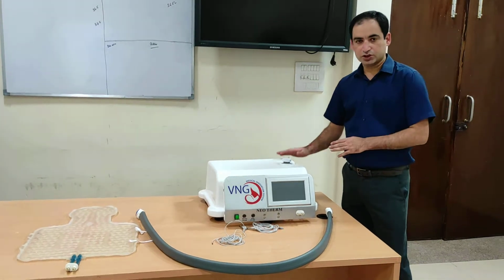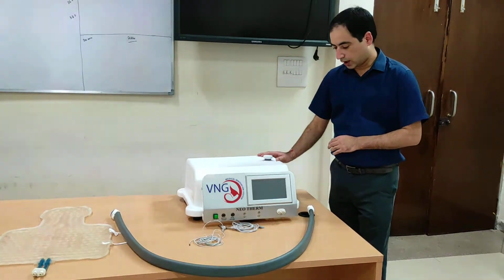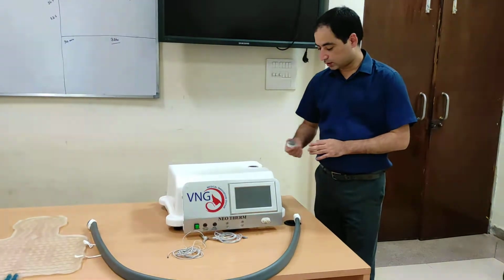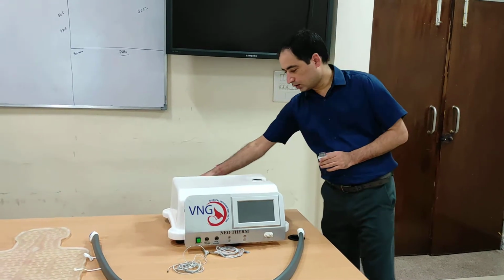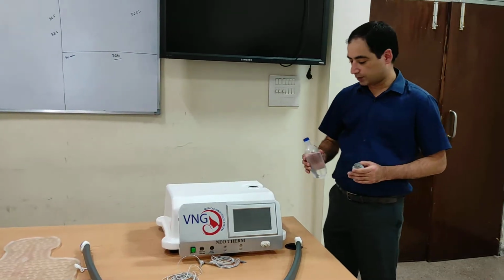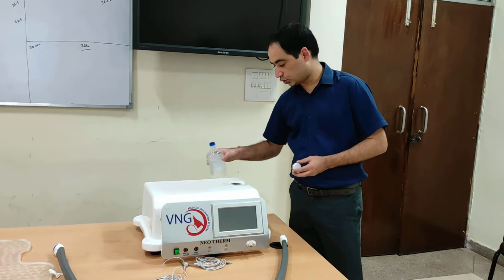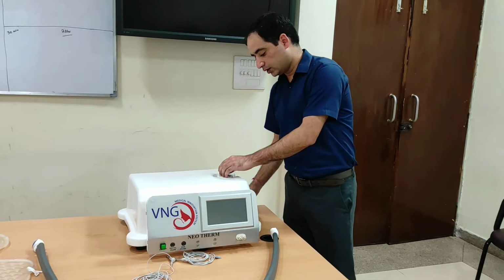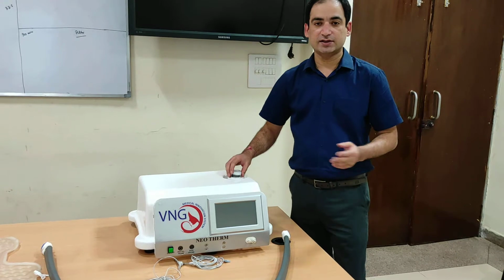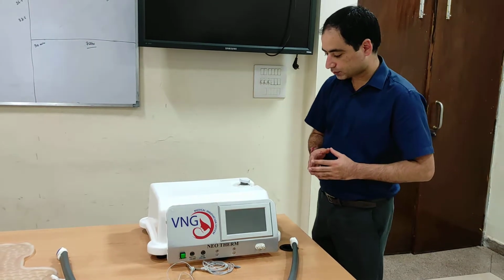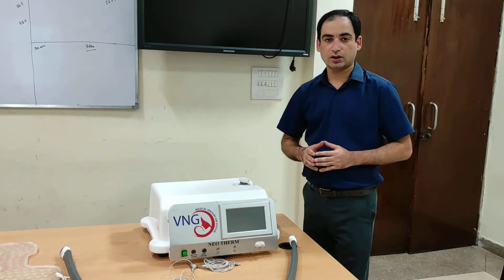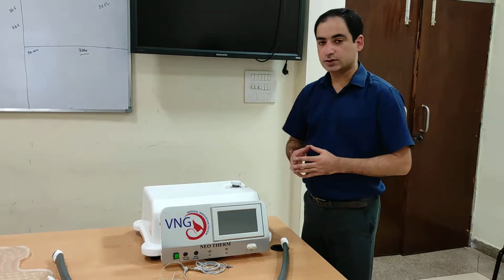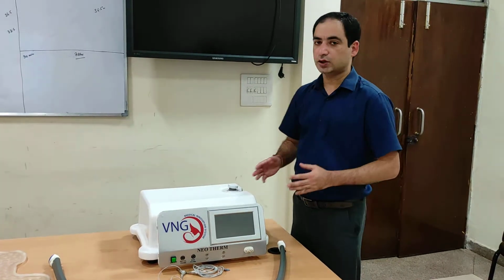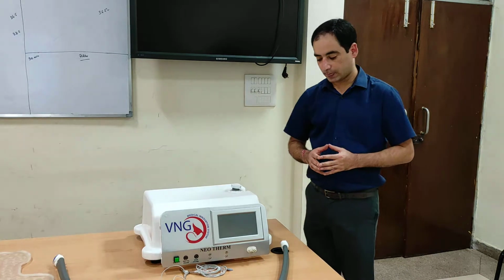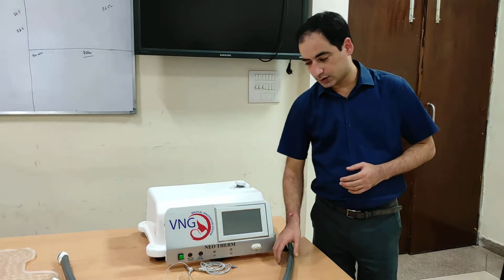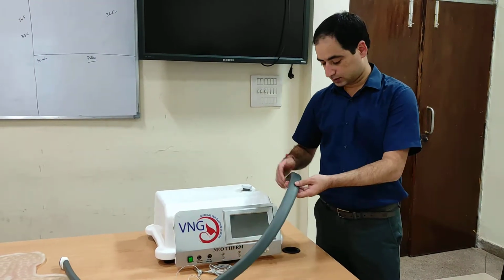So coming to the main machine, usually the coolant is filled at this place. Usually about 500 ml to 1 liter of coolant has to be put on this machine, and usually one filling suffices for 5 to 6 therapies. Since this machine does not come with a battery backup, it is advisable that this is connected to the UPS for use.